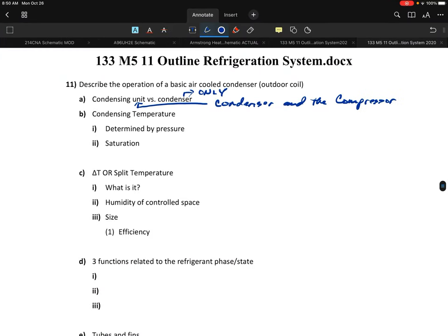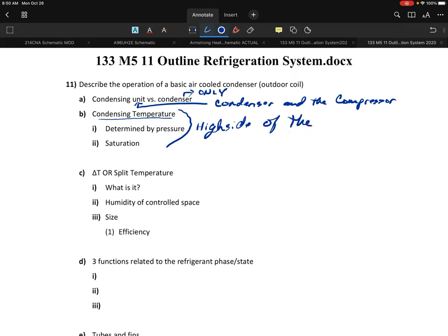So that's a little bit on the condenser. One of the things we talked about is the term condensing temp. We always consider the condensing temp to be generally referred to as the high side. When we talk about what is your condensing temp, we're referring to the high side of the system. How do we determine that condensing temp? Simply by the pressure on your high side. Whatever that pressure is, we find out what they call the saturation temperature — that's what the condensing temp is.